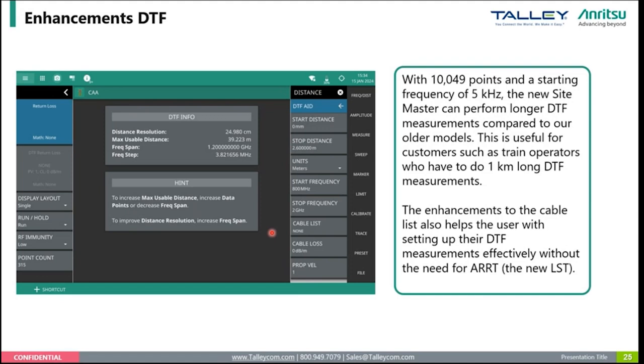As you can see here, we can definitely do more than a kilometer in distance-to-fault measurement. Of course, this heavily depends on the loss of your cable. Theoretically, with a zero loss cable, it'll be 5 kilometers, but in reality there's no cable with zero loss. So it's entirely based on what your cable is.